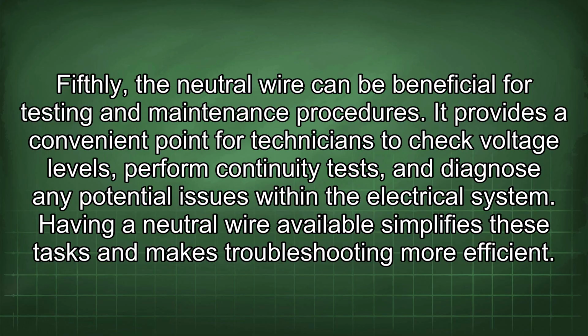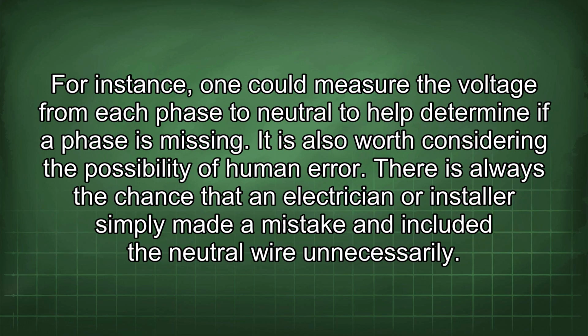It provides a convenient point for technicians to check voltage levels, perform continuity tests, and diagnose any potential issues within the electrical system. Having a neutral wire available simplifies these tasks and makes troubleshooting more efficient. For instance, one could measure the voltage from each phase to neutral to help determine if a phase is missing.